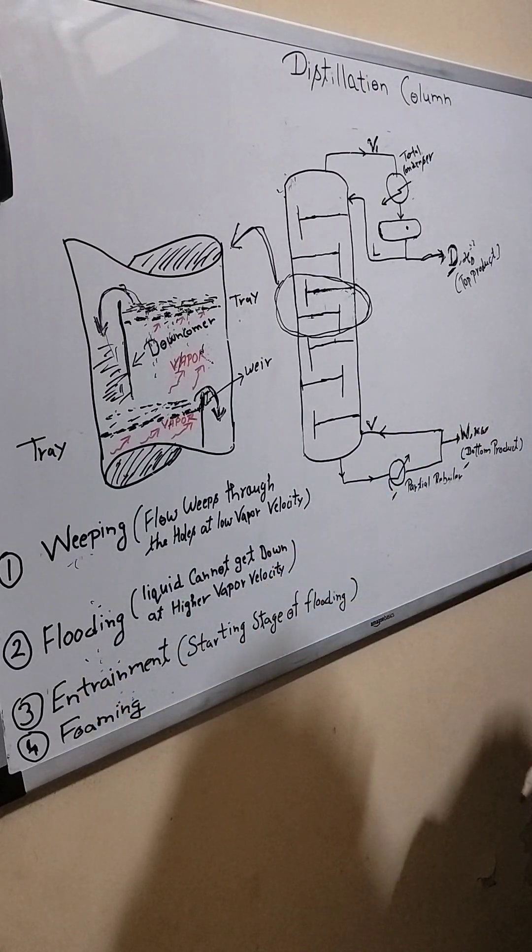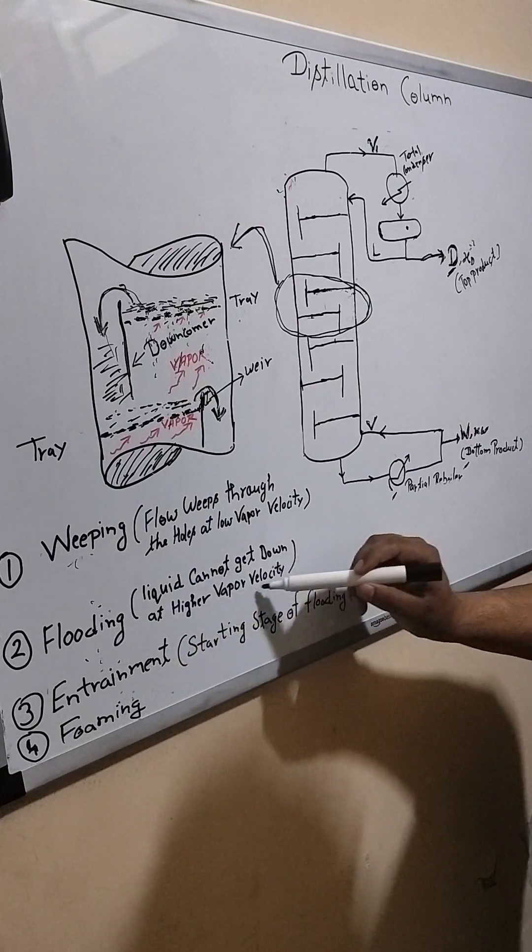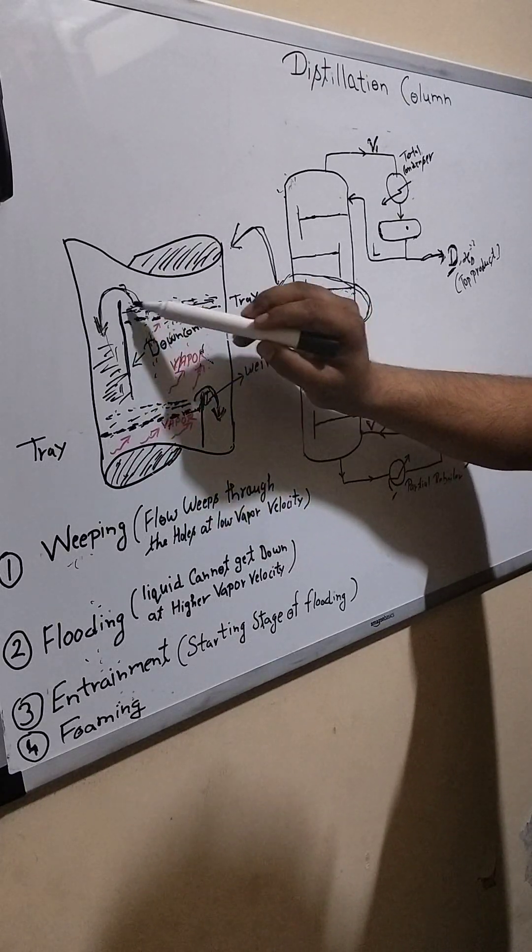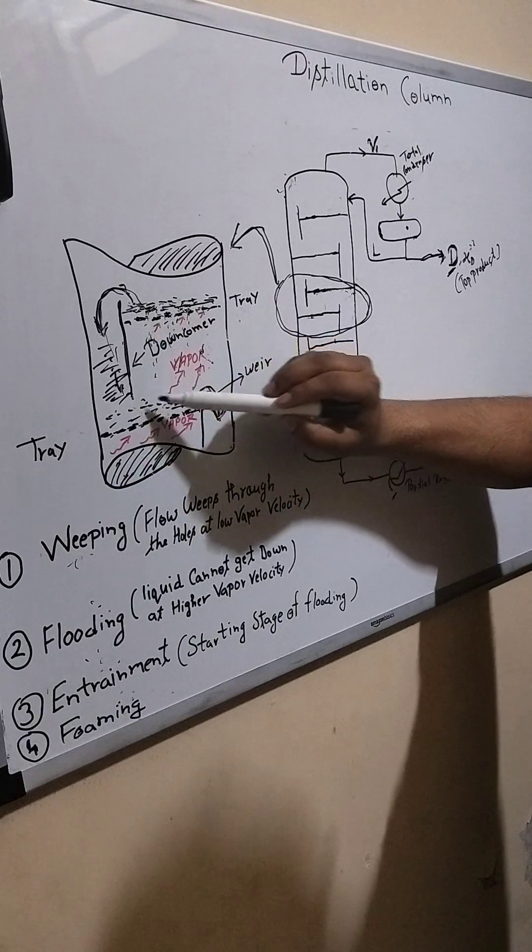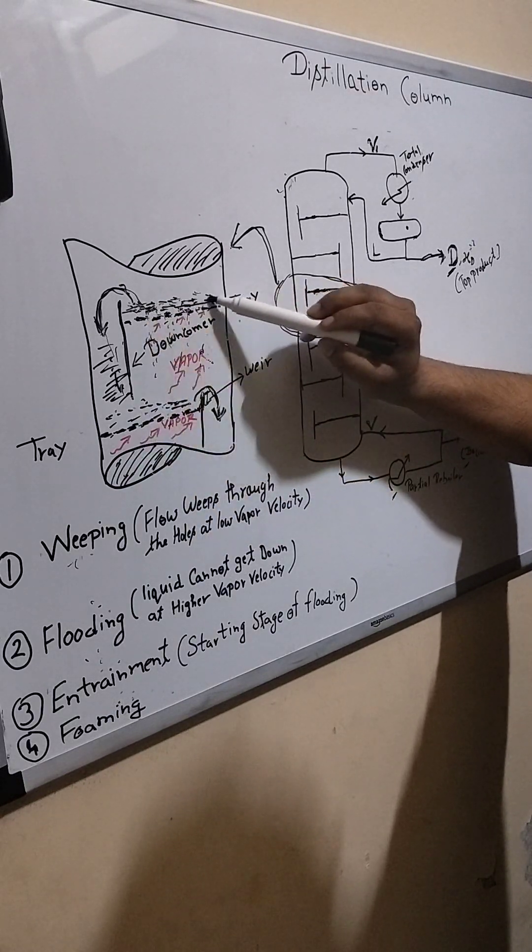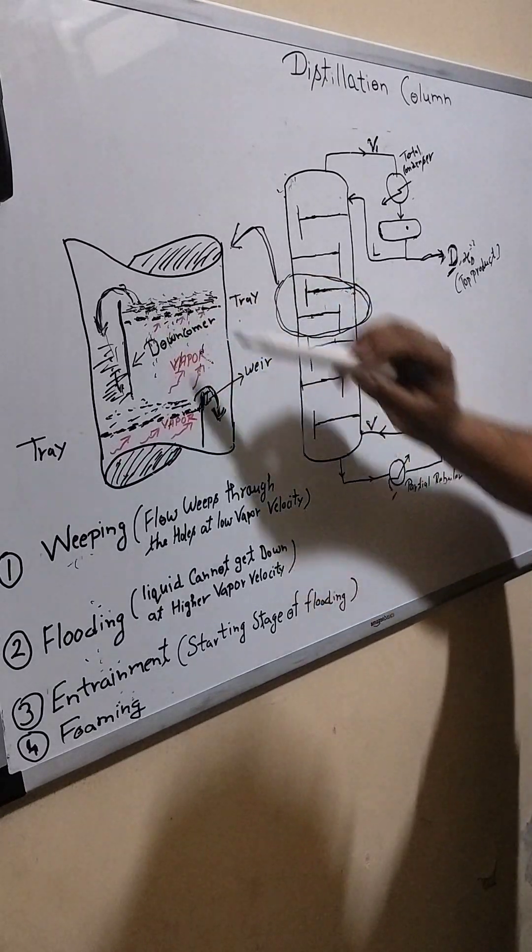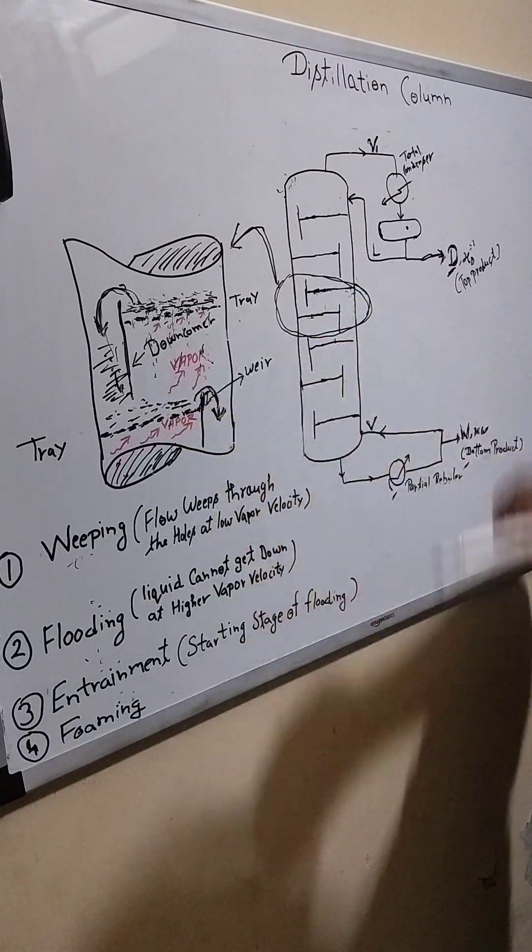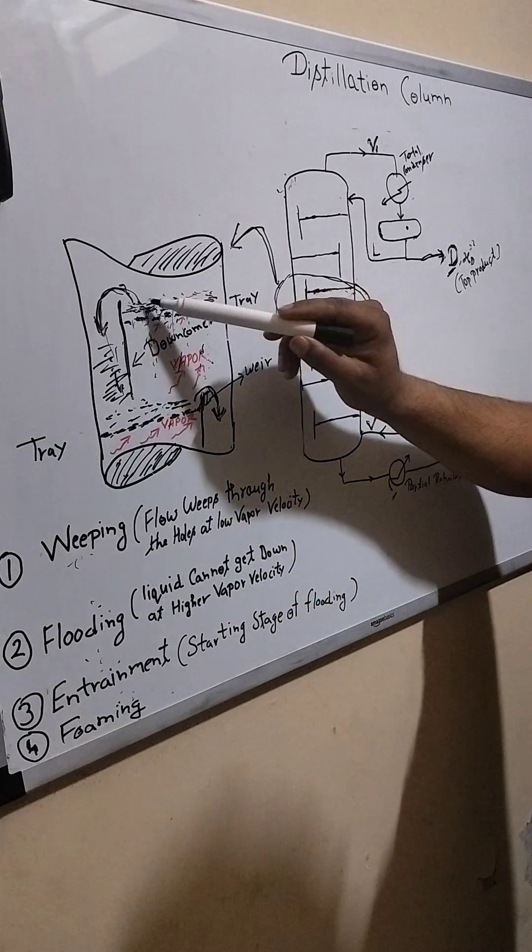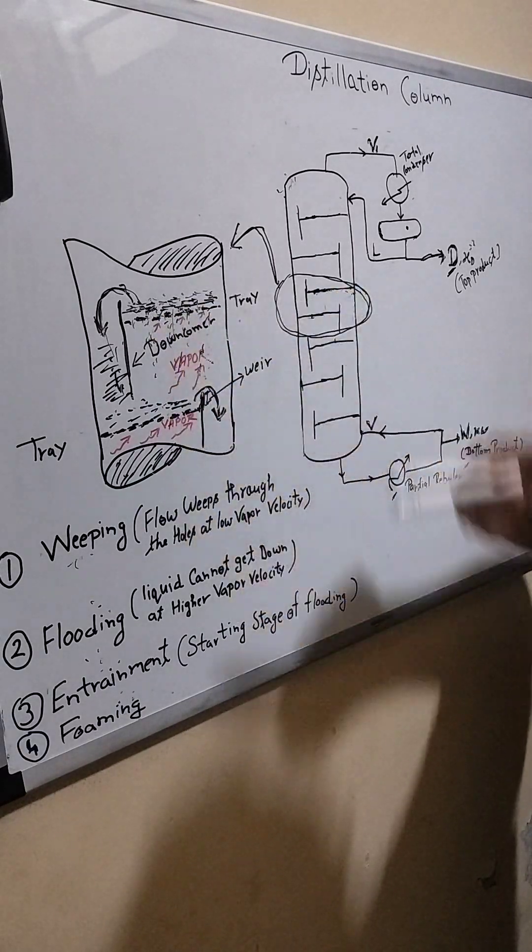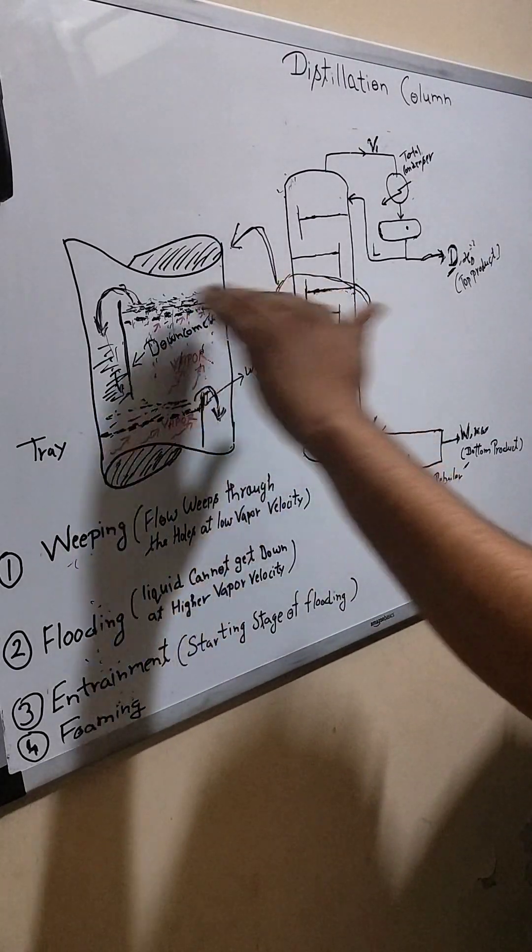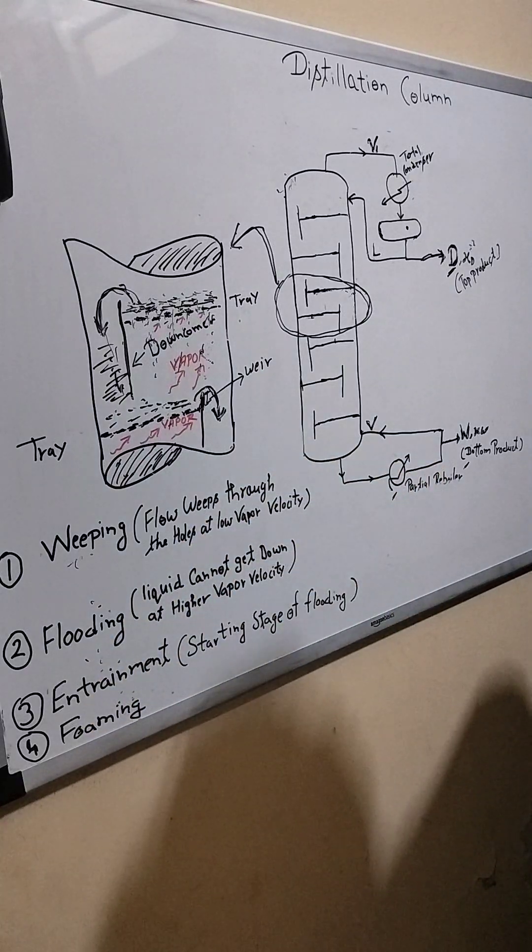And second is flooding. When flooding occurs, liquid cannot get down at higher vapor velocity. Suppose if your vapor velocity is very high, the liquid cannot move in the downcomer, so it will hold here. It cannot move through these holes because vapor velocity is very high. So if the liquid will hold in all the trays, your mass transfer will not occur. You will not get the desired separation which you require.